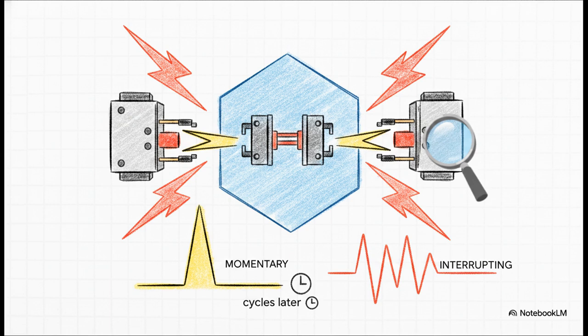Then you have the interrupting rating. That's what the breaker must actually clear a few cycles later when some of the DC offset has decayed and we're closer to a symmetrical RMS value. To figure this out, engineers rely on the E over X method as a standard shortcut, basically applying a multiplying factor to convert a simple symmetrical fault calculation into a properly conservative asymmetrical rating requirement.